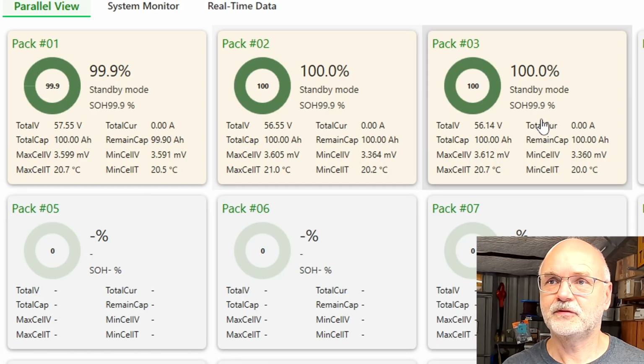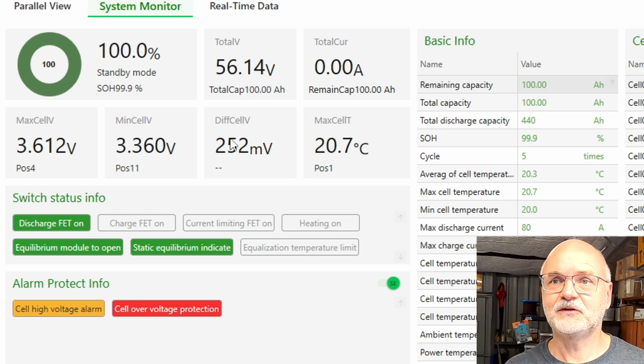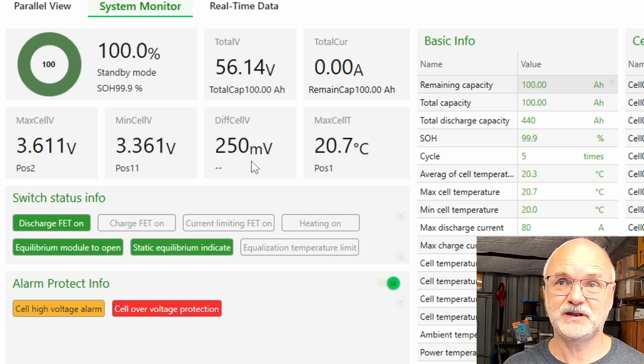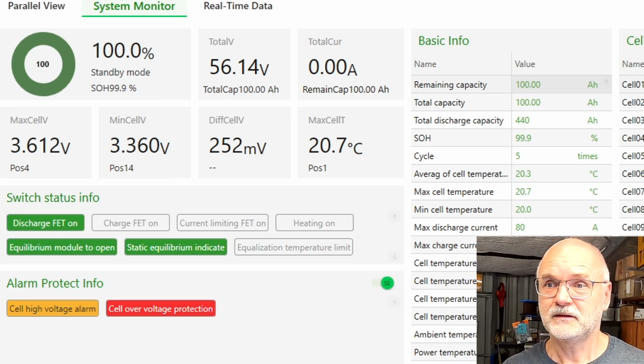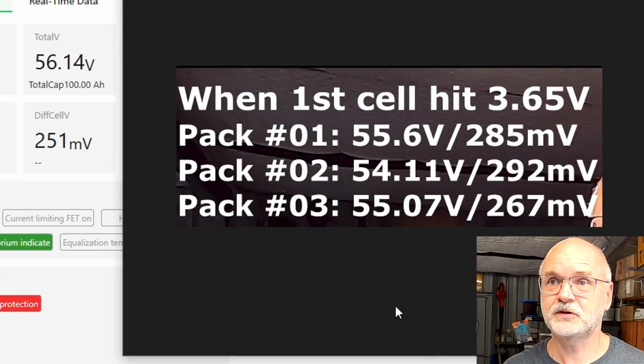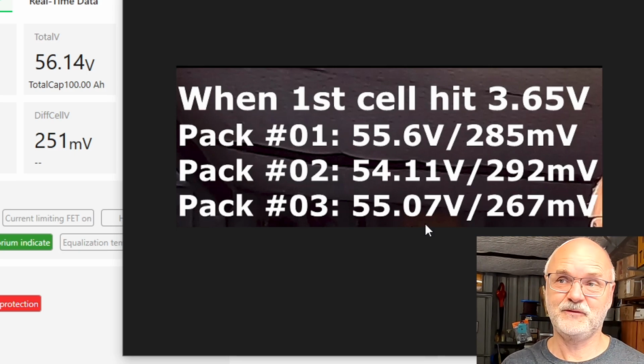We'll have a look at pack number 3. Same situation, still a cell over voltage protection, so one of the cells reaches 3.65 volts. We've got 250 millivolt deviation still, but we are at 56.14. Looking at our screenshots, pack number 3 was at 55.0 before, so we can charge the pack already over 1 volt higher now than before.